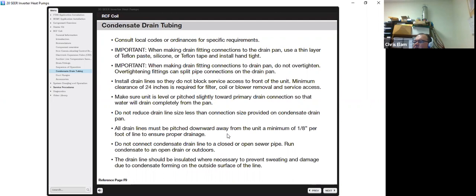Always make sure they're pitched downwards all the way through, at least 1/8 inch per foot, to ensure proper drainage. Again, do not connect the condensate drain line to a closed or open sewer pipe.